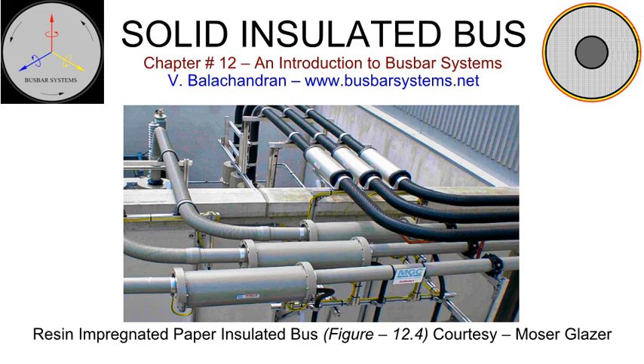End termination. End terminations are specific to the location, indoor or outdoor, and connected equipment. Outdoor: connection to switchyard equipment, medium voltage and high voltage; transmission line, medium voltage and high voltage; transformer bushing, medium voltage and high voltage; transformer cable box, medium voltage. Indoor: connection to switchgear panel, medium voltage; gas-insulated switchgear, medium voltage and high voltage. Manufacturers have standard designs for end terminations with adapter box for different current and voltage ratings that are customized to suit the connecting equipment. Support system.